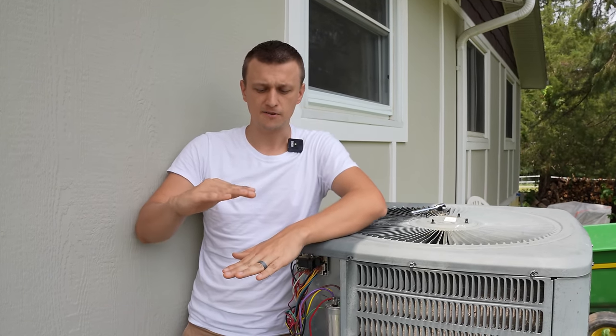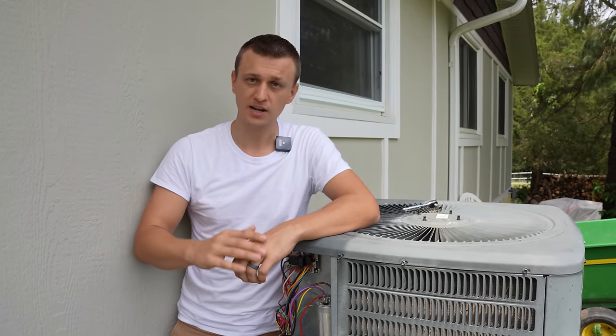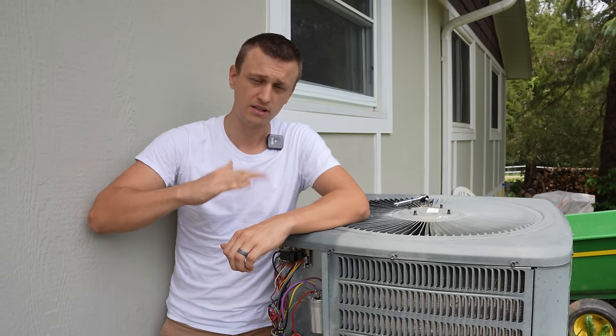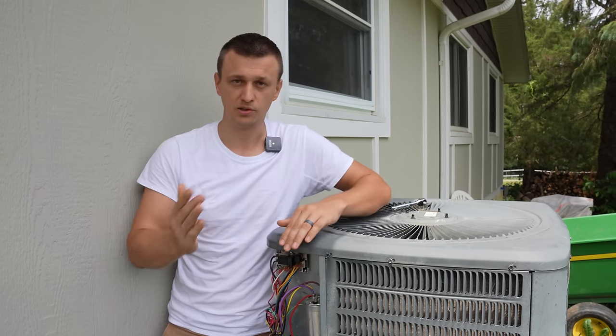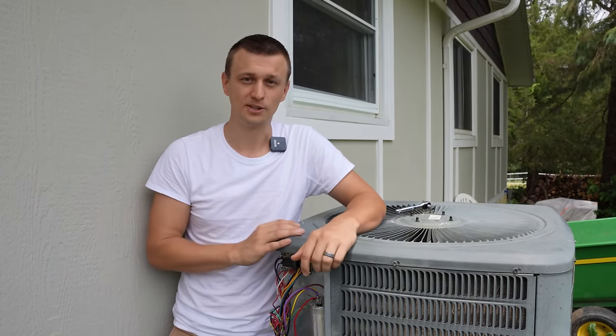Another time I had a piece of insulation from the bottom of the furnace come undone, just one corner. And every time the blower motor comes on, you would just hear that thing flapping away really fast. They thought something was really wrong, but really it was just that thing. So I secured it back down with just some tape and everything was good.